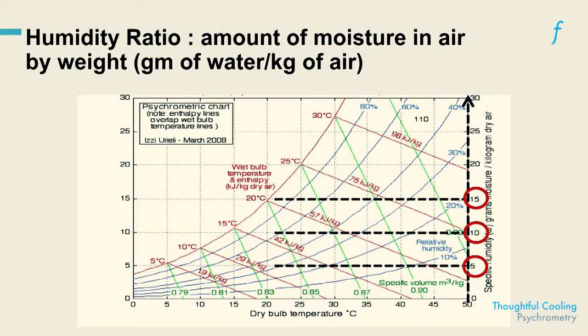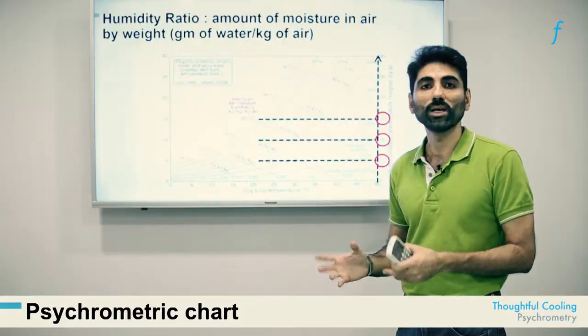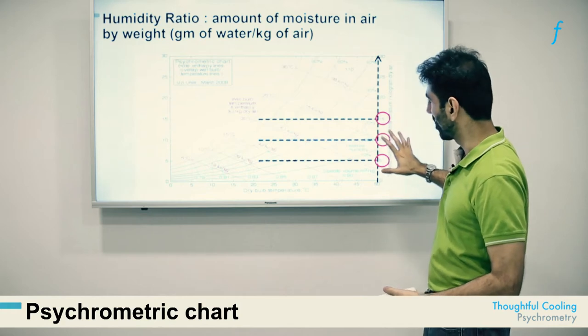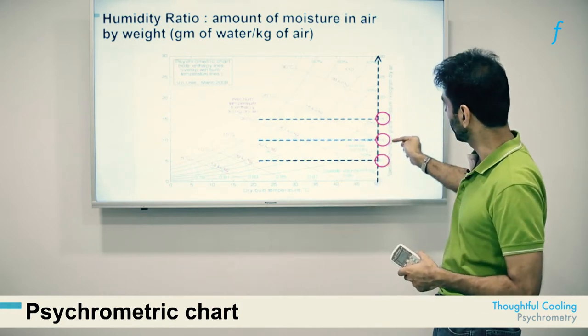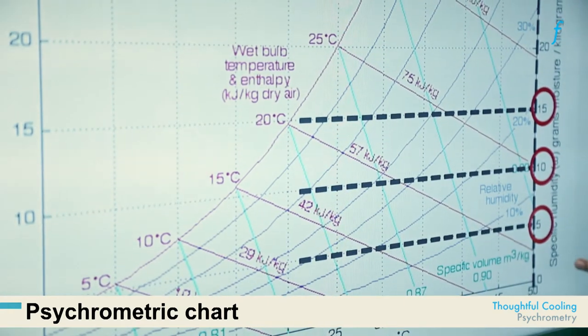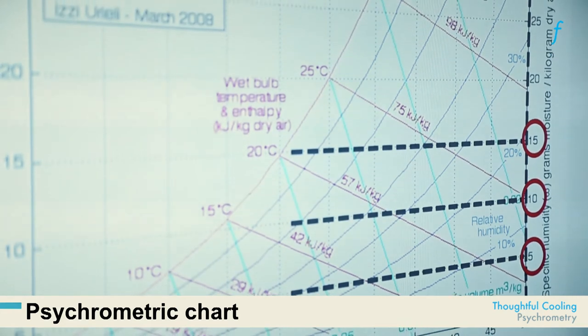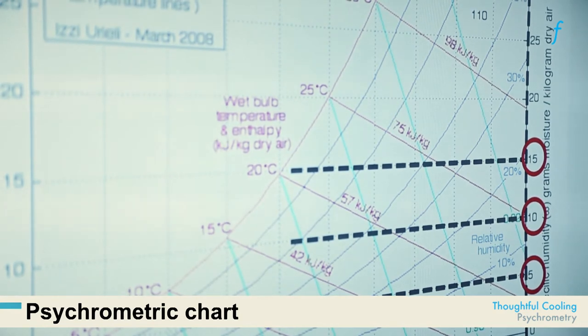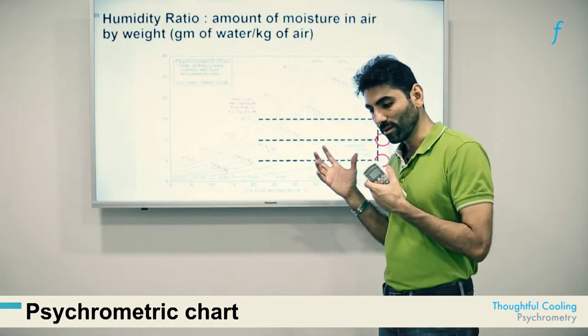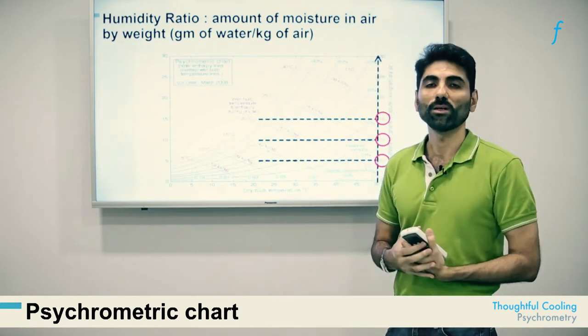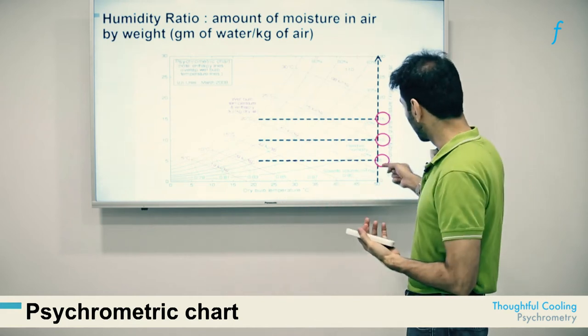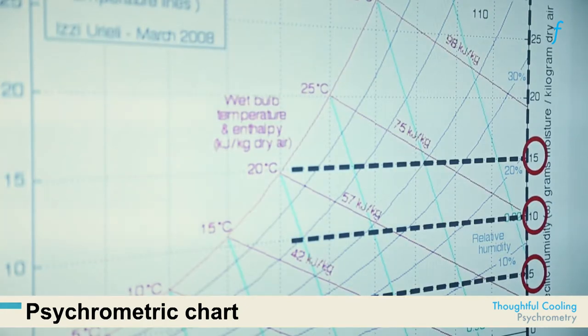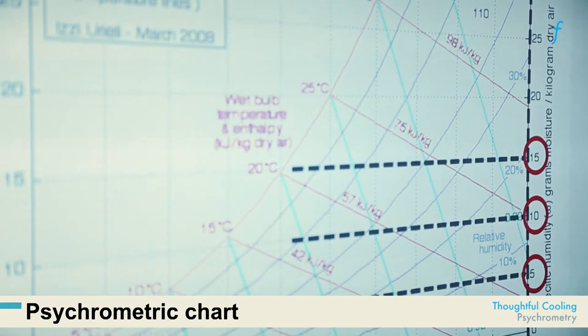Now for the humidity aspect of psychrometrics. The first piece of humidity information — the third layer overall — is called specific humidity, on the y-axis, in units of grams of moisture per kilogram of air. These are very small levels; for example, 5 grams of moisture per kilogram of air. But in the study of buildings, small increments in these values can lead to significant thermal discomfort, so they are very important on a relative scale.